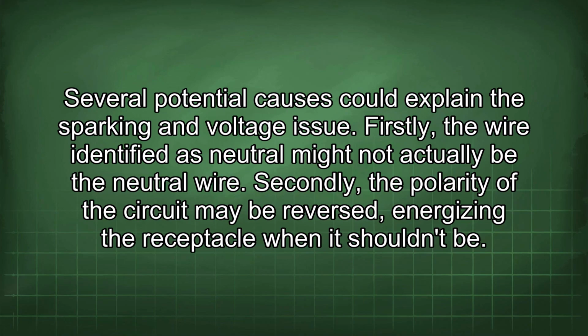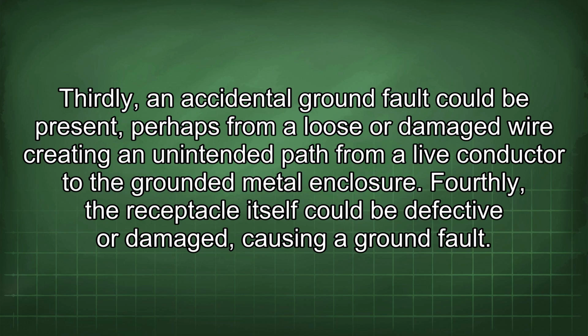Several potential causes could explain the sparking and voltage issue. Firstly, the wire identified as neutral might not actually be the neutral wire. Secondly, the polarity of the circuit may be reversed, energizing the receptacle when it shouldn't be. Thirdly, an accidental ground fault could be present, perhaps from a loose or damaged wire creating an unintended path from a live conductor to the grounded metal enclosure.